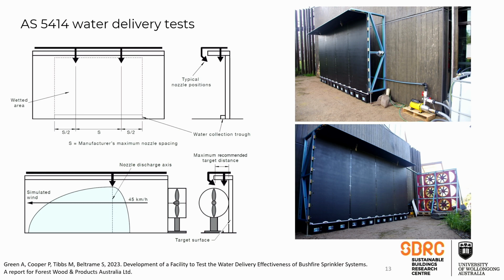In the second test, you install a fan to generate a simulated crosswind of 45 kilometers per hour, and ensure an individual sprinkler can wet the wall directly below itself—the water isn't all blown downwind from the sprinkler location. In the photos, you can see our test wall, and in the lower photo, the 6 fans we used to generate that crosswind.